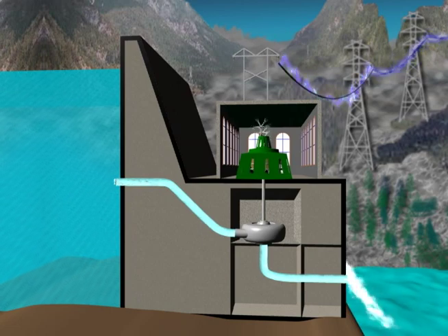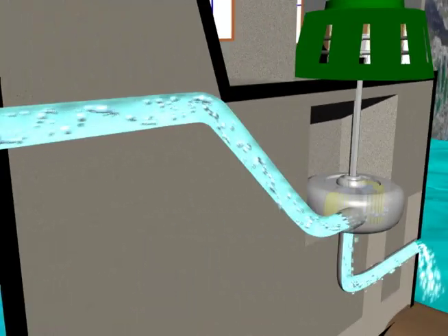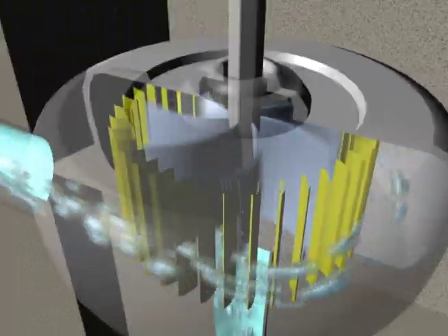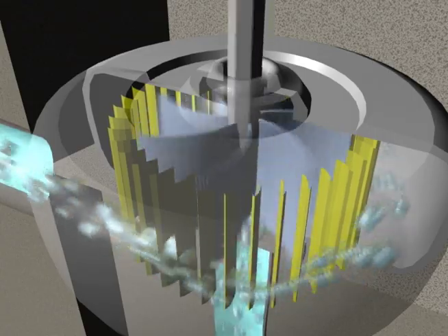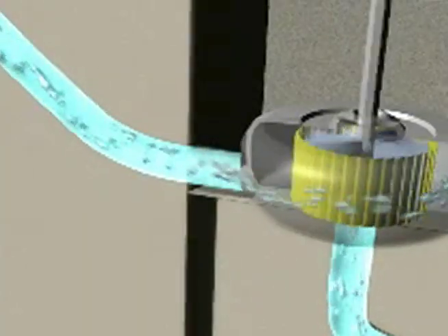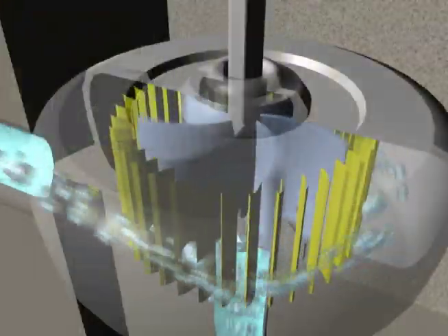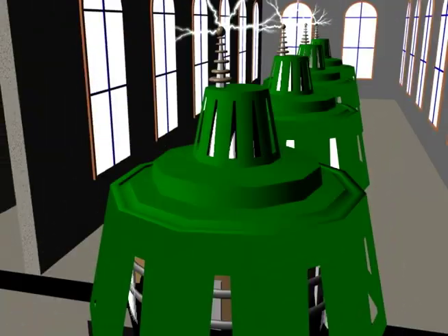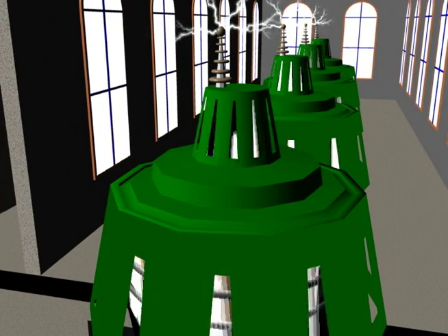Here's how they work. Water is stored behind a dam. To generate power, the water is directed through tunnels called penstocks. The penstocks bring the water to the powerhouse turbines. At the turbine, vanes called wicket gates control the water's energy and direct the water into the turbine runner's blades, causing the turbine to spin a shaft connected to a series of large magnets in the generator.